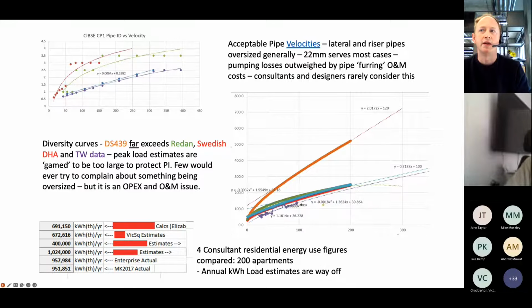So what happens when you oversize? You slow flows through pipes, you end up getting furring, you get excessive losses, you get plates failing to get turbulent flow and effective heat transfer. You get pumps that are oversized and are unable to turn down below 30%, so they're running too fast. You end up getting bypasses that are open too much because of this, or you get pumps being deadheaded and breaking and overheating. You get boilers which are sort of oversized and prone to cycling.